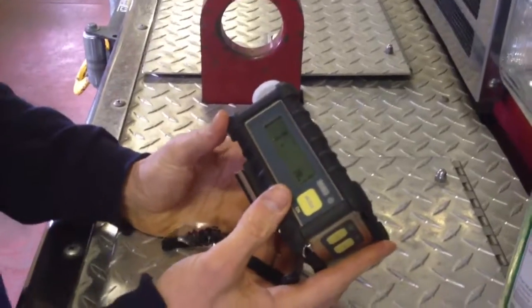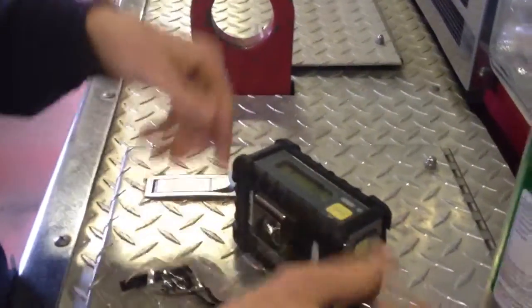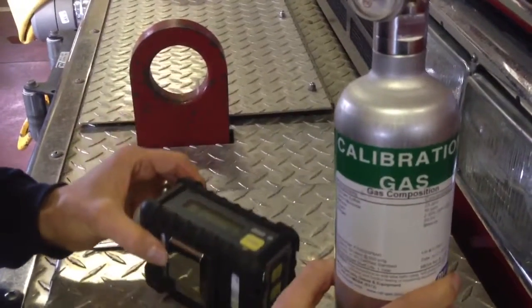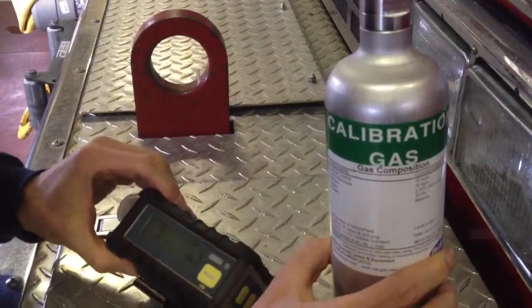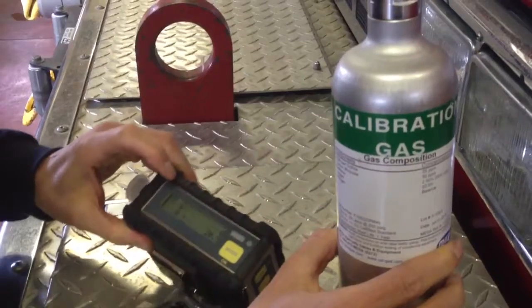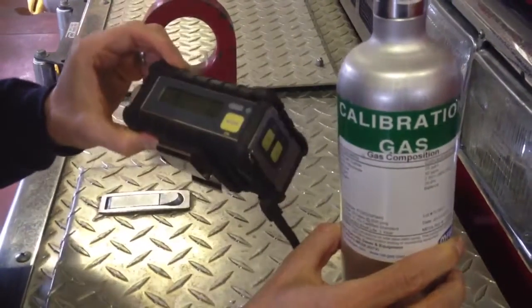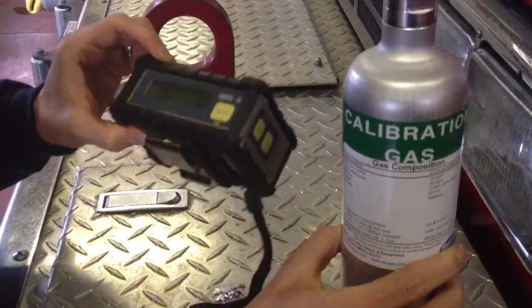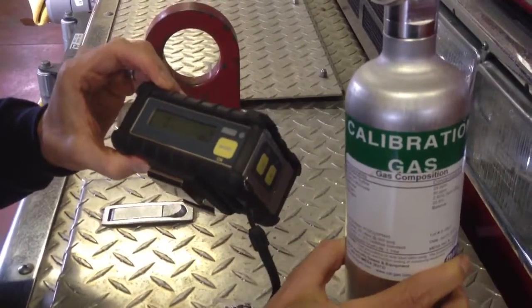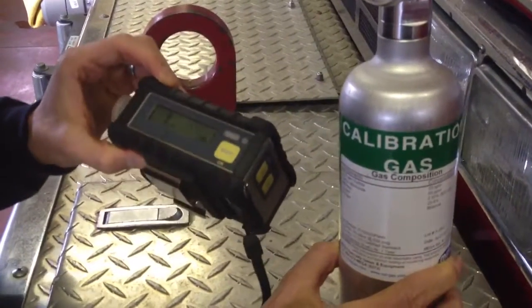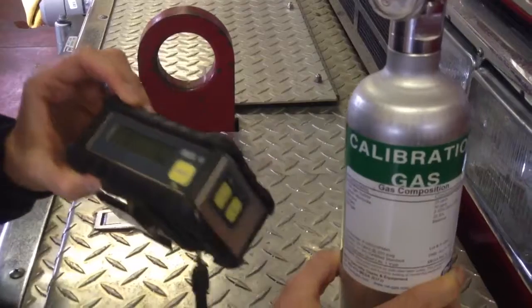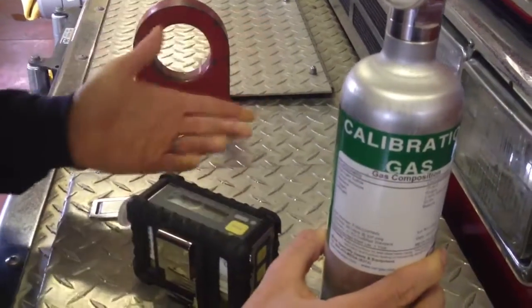The bump test makes sure the gas detector is actually going to read what it's supposed to read. We do this because some of these sensors fail to 0, and if you didn't bump test it, you could potentially go into an IDLH atmosphere and not know it, and deem an area safe that actually isn't.